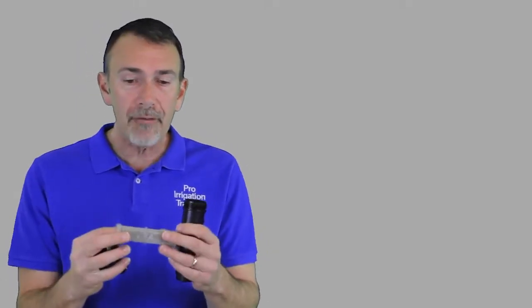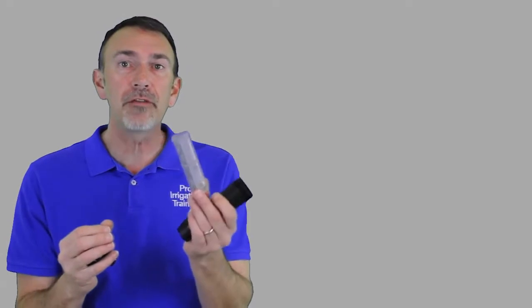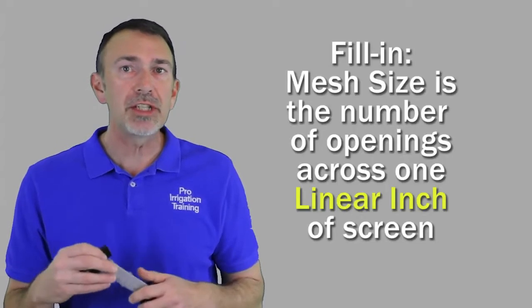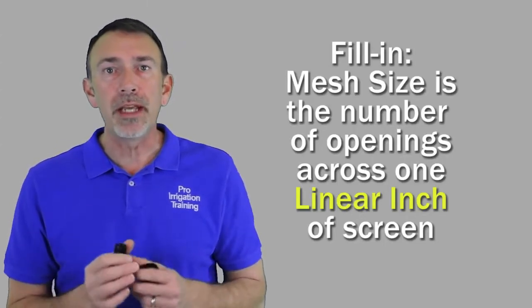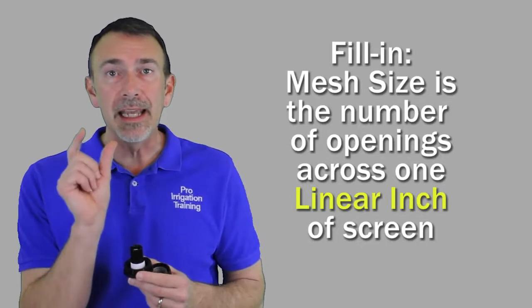So what we have here is a 200 mesh filter. Let's take one moment and define a couple of these terms before we get too far into this. When you get a mesh size on a filter or some other type of product, what the mesh size refers to are the number of openings on a linear inch. Now listen to what I'm saying - it's a linear inch, not a cubic inch. So the mesh size, if you take one line one inch long and count the number of openings along that line, that'll get you the mesh size.